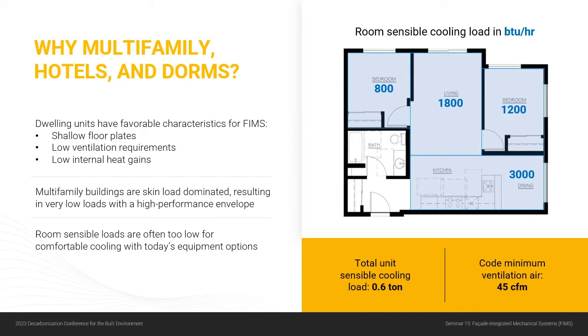Now, we've been talking about multifamily buildings, which also includes hotels and dorms, and it's important to point out why we're targeting that for now. The multifamily buildings have characteristics that are very favorable to this kind of system. For one, they have shallow floor plates. If we're conditioning a space completely from the facade, that would be difficult to do if we had deep floor plates. But fortunately, in multifamily buildings, you typically don't have that.